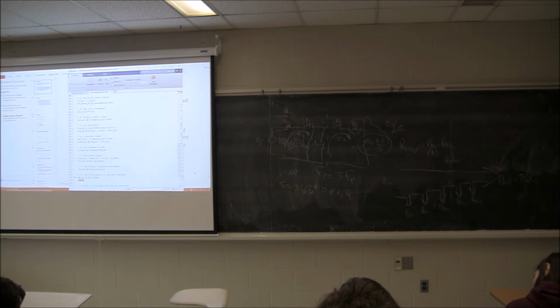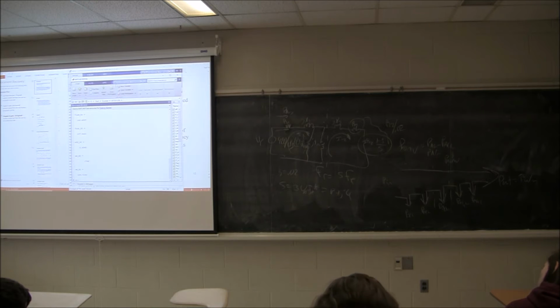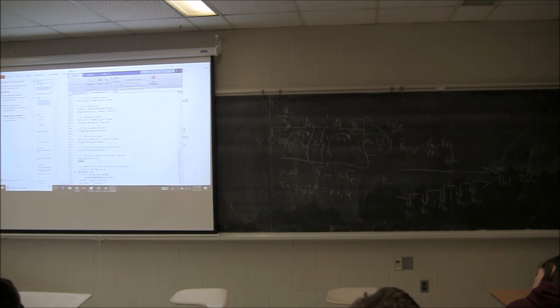Now I have rotational RPM and synchronous speed, which gives mechanical speed, which I've already defined previously, to help with some of the calculations. It spins at 1764 RPM or 184.7 radians per second. And the last thing from the problem description is, what is the starting KVA code of the motor?